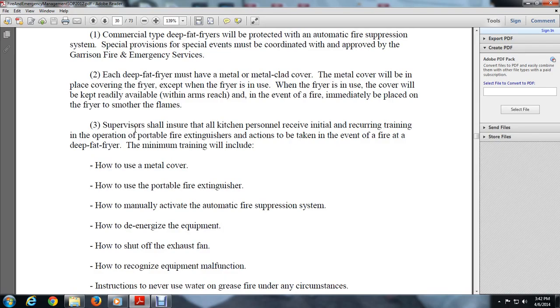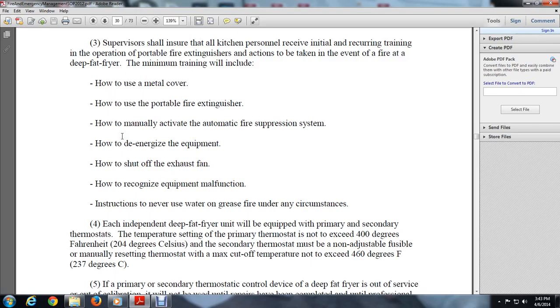3. A supervisor shall ensure that all kitchen personnel receive initial and recurring training in operating portable fire extinguishers and actions to be taken in the event of a fire at the deep fat fryer. The minimum training will include how to use a metal cover, how to use a portable fire extinguisher, how to manually activate the automatic fire suppression system, how to de-energize the equipment, how to shut off the exhaust fan, and how to recognize equipment malfunction. Instruction: never use water on a grease fire under any circumstances. 4. Each independent deep fat fryer unit will be equipped with primary and secondary thermostats.